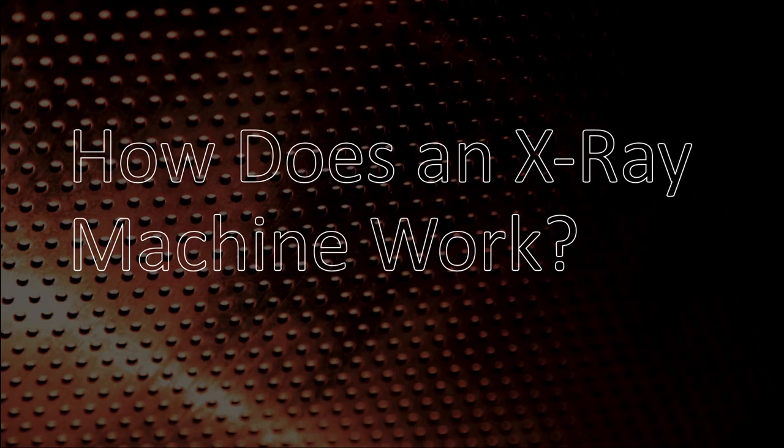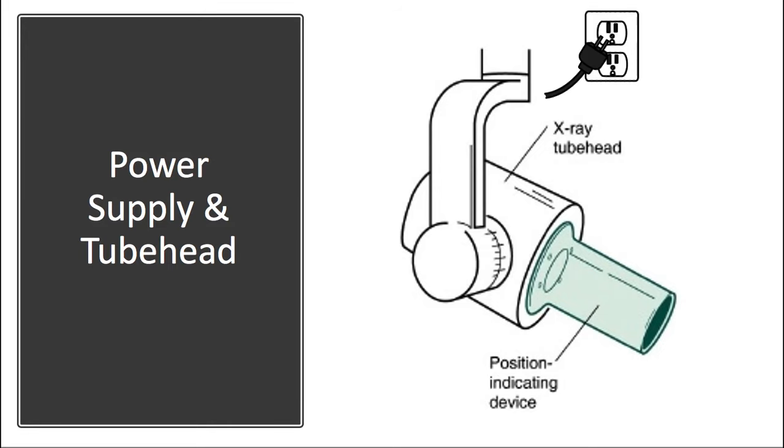So first we're gonna start with the big picture. How does an x-ray machine work? So we have a high voltage power supply that powers up the x-ray unit. The position indicating device is just a plastic casing that allows you to line up the x-ray unit to the proper location and distance from the patient's mouth.